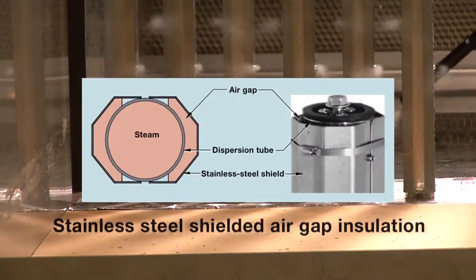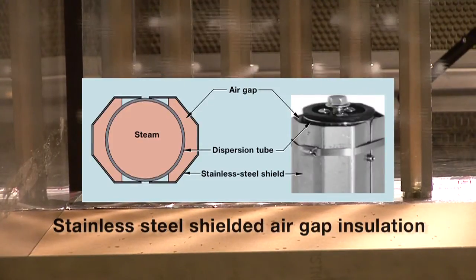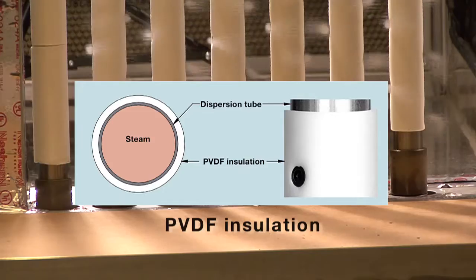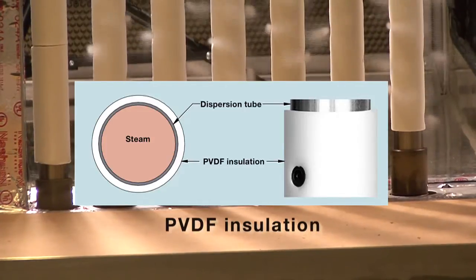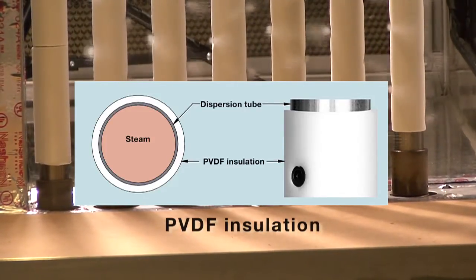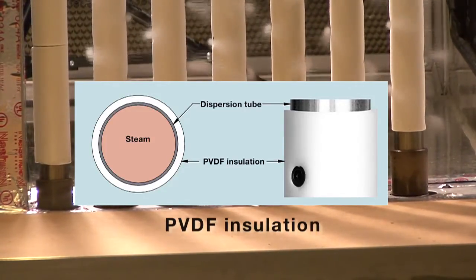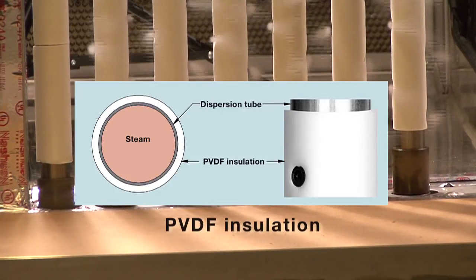The dispersion assembly on the left insulates tubes with stainless steel shields, which creates an approximate one quarter inch air gap between each tube and its shield. The dispersion assembly on the right insulates tubes with one-eighth inch thick PVDF insulation, which traps air in thousands of small pockets.